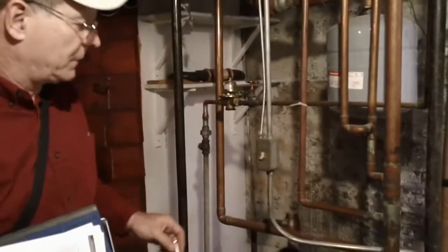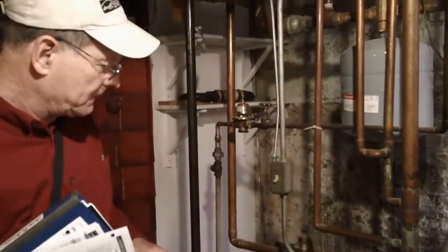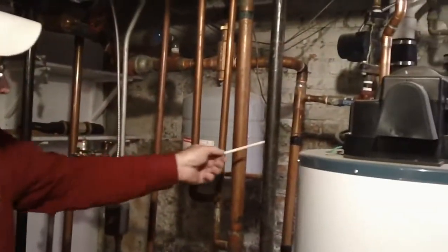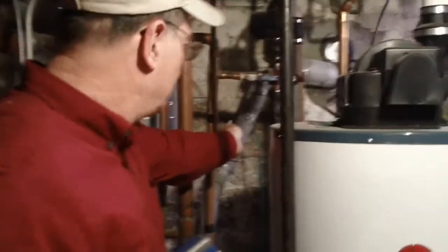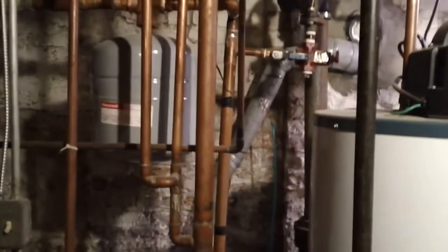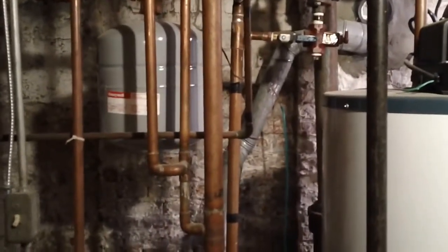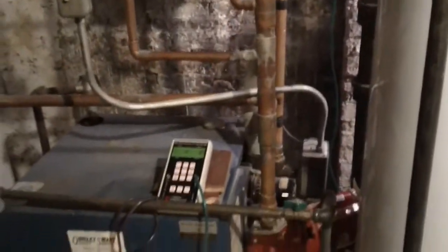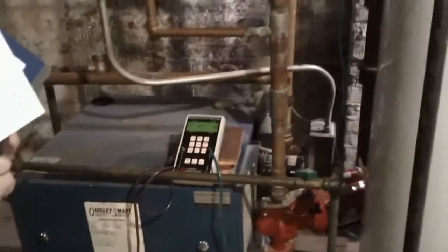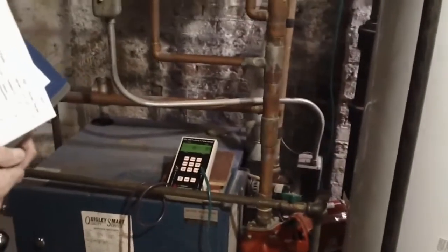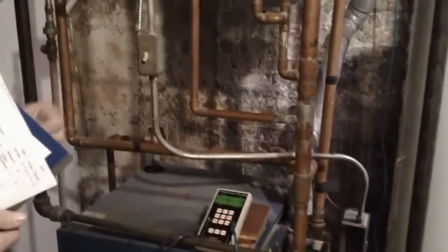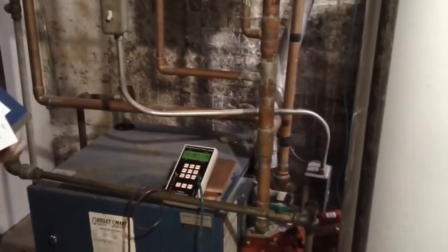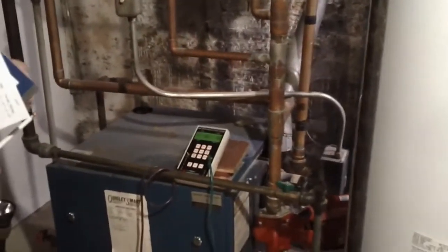Now we're set up to do a combustion safety test on this boiler. And the boiler vents into a chimney. So over here you can see where we've got a probe put into the vent pipe to measure draft pressure. And we have a hose to the outside which calibrates our pressure to the house. So right now we're going to note some readings here, and then we're going to close and open doors and just see how this boiler works and how it drafts after we do that during our test.